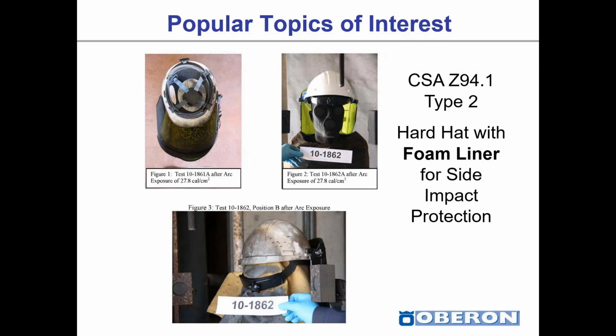Now, I actually asked them to turn it around backwards so we can expose the suspension as well as the hard cap itself to the full extent of that thermal energy. And you see in the bottom image, we still don't have any melting, dripping, or anything that would have caused any concern. So the incident energy exposure was no greater than, say, 28 calories. Mind you, you should never be wearing an arc flash face shield for exposure greater than 12 calories.